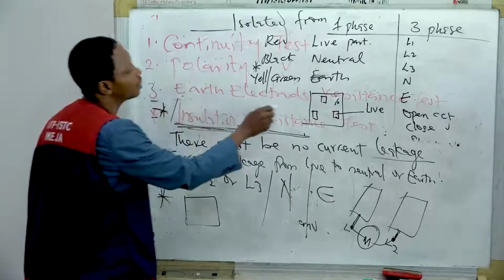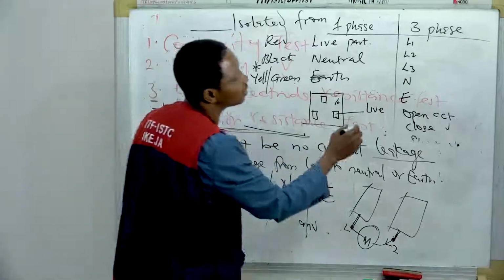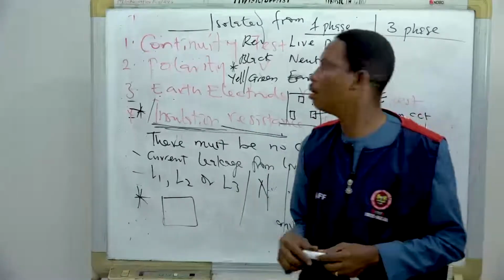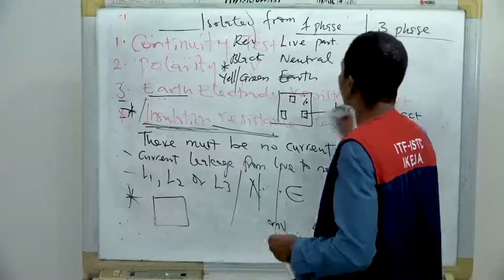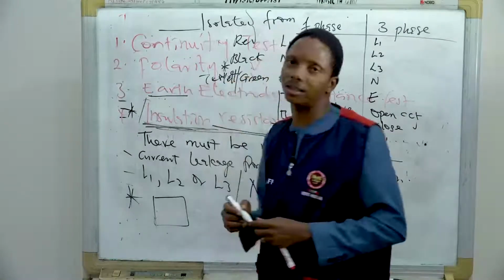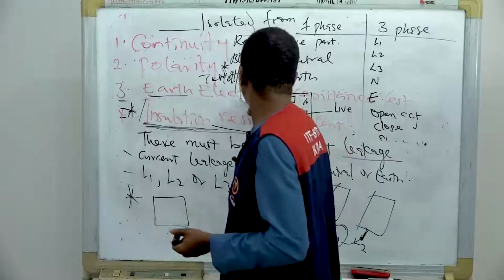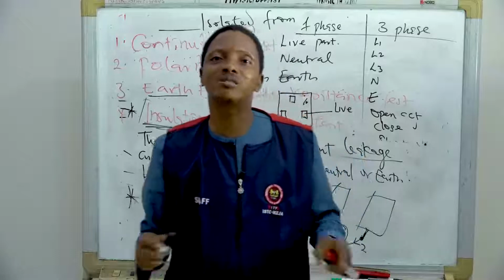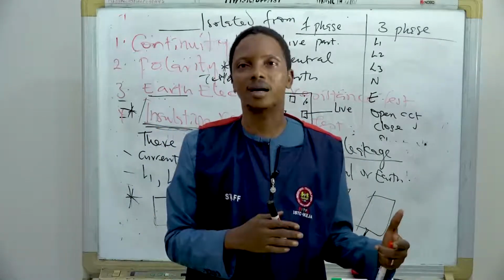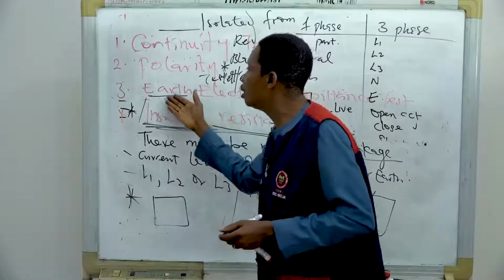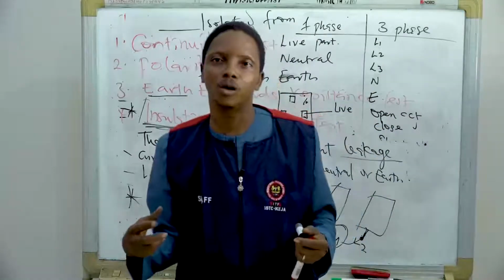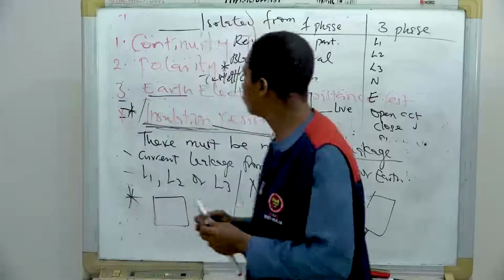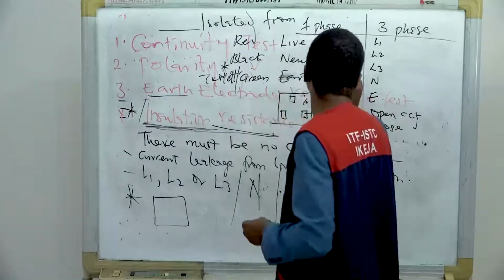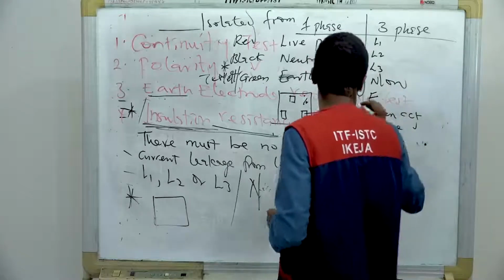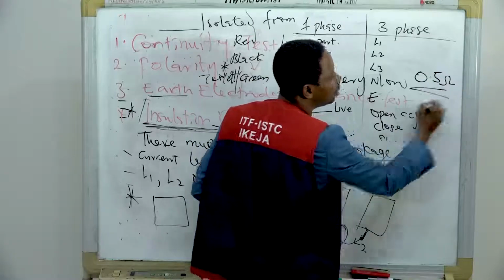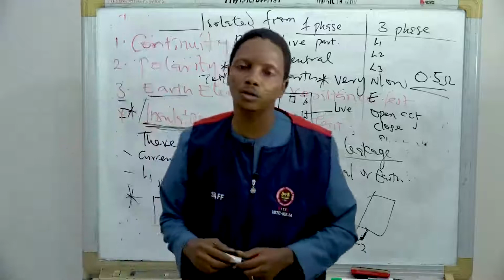And finally, earth leakage. The last one is earth electrode resistance test. For this, we have a special meter. We call it an earth tester. It's a special meter that is used in carrying out earth electrode resistance test. I will explain this more by the time we are in our practical session. But what I will say is it is used to determine the soil resistance of the earth connection, because the soil resistance must be very low. In fact, we have a range for a transformer, it must not exceed 0.5. In demonstration class, I will show you how it is being used.